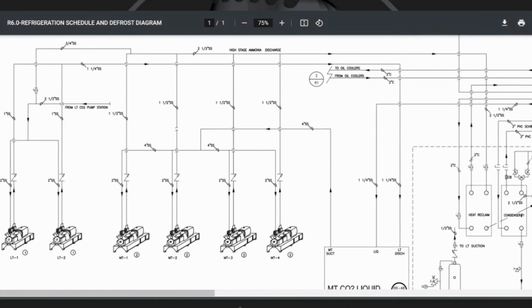I guess probably the medium temp, right? And then we can go to the low temp, which then we can feed back through the compressors. Sure. The four compressors are tied in parallel, and the discharge line goes right from the compressors over to the condensers. Well, it goes to the heat reclaim heat exchanger first.